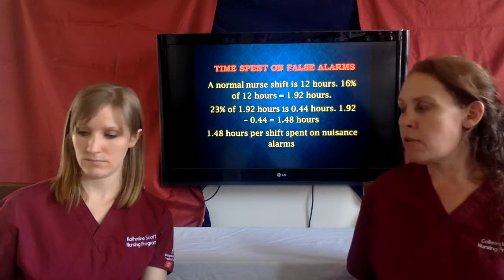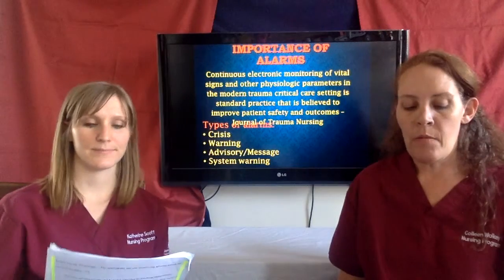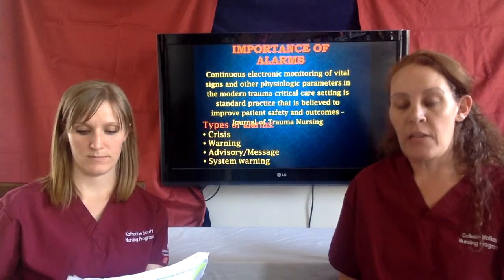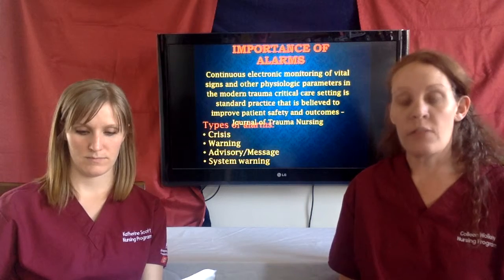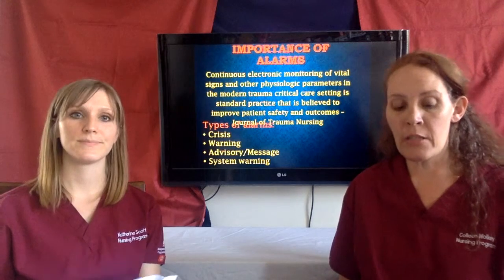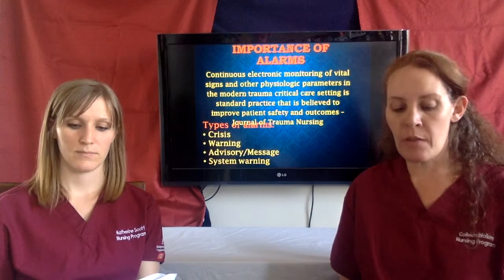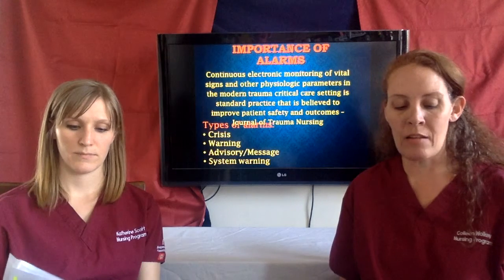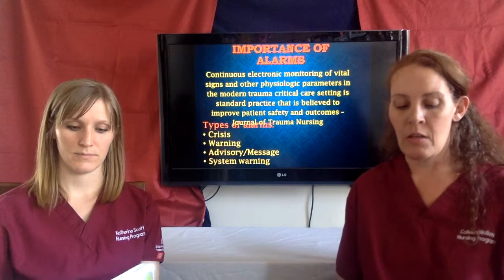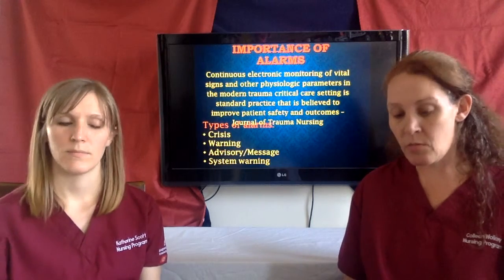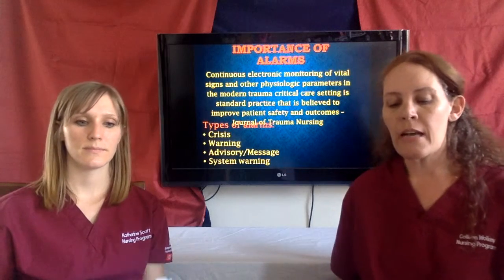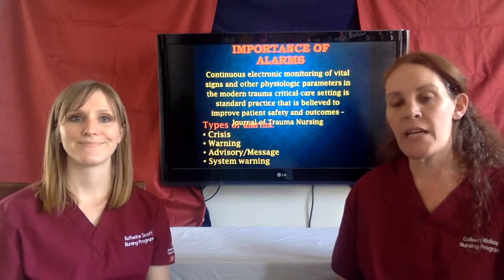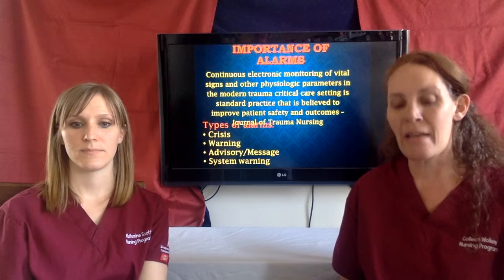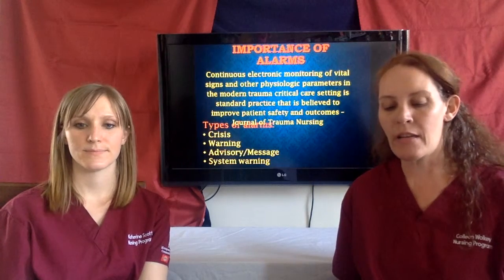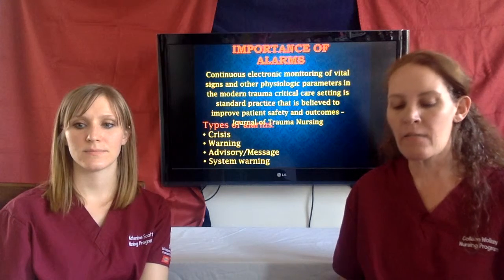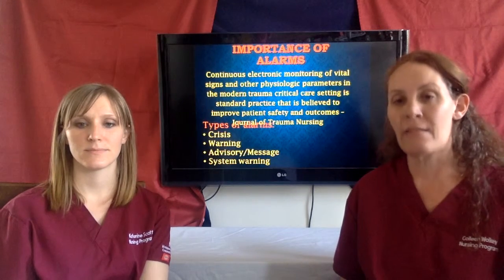Now, let's talk about the importance of alarms and different kinds of alarms. I want you to think about all of the devices used in patient care. Just to name a few, there's vital sign monitors, pulse oximeters, ventilators, infusion pumps, feeding pumps, call bells, bed alarms, and that's just naming a few. All of these devices have alarms or even multiple alarms. Collectively, the devices in use on a single patient can produce hundreds of alarms every day. On an entire unit, the number of daily alarms can easily reach into the thousands or tens of thousands.